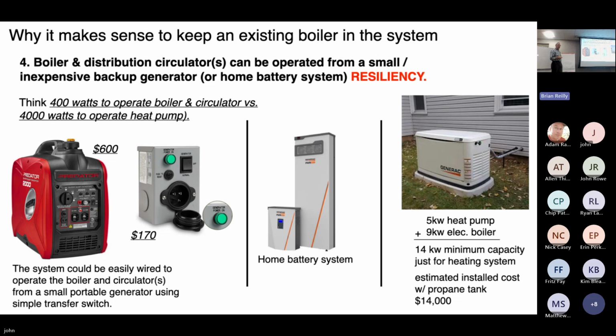And some of the other products that are coming into the market this coming year will have electric resistance heat built right into them. But many of them don't go beyond 6 kW. And 6 kW is around 20,000 BTUs an hour. So if it's a small, well-insulated house, that's probably sufficient. If it's 10,000 square feet, it's not going to do much. Yes.